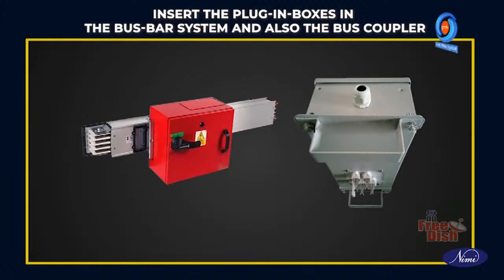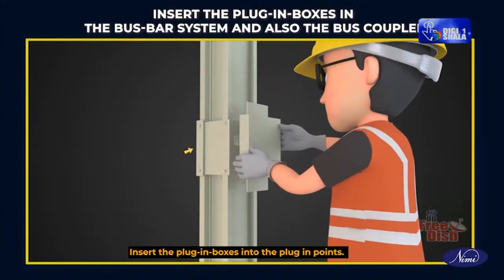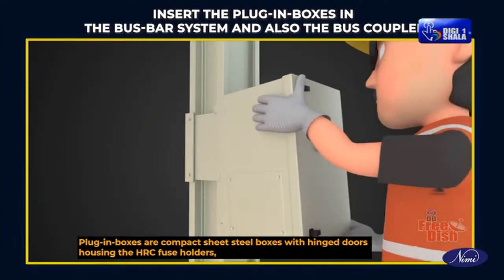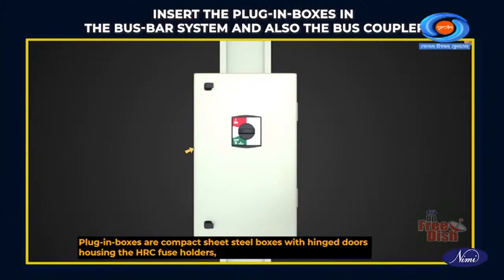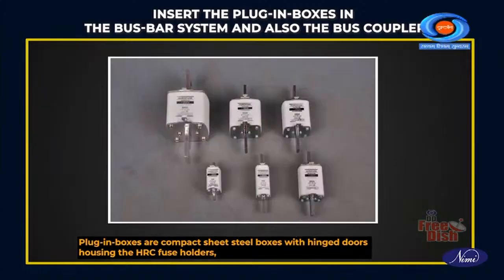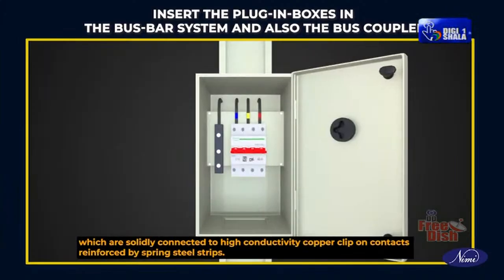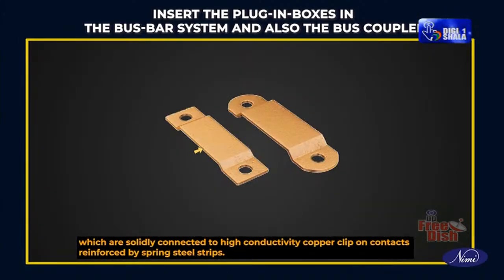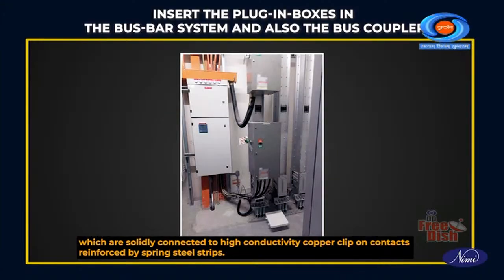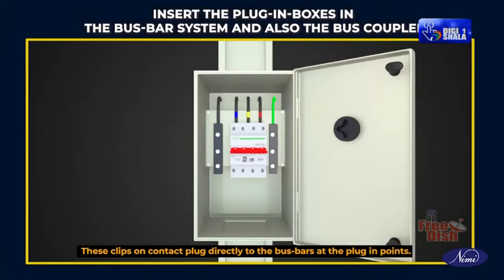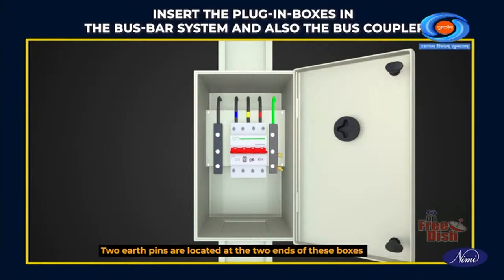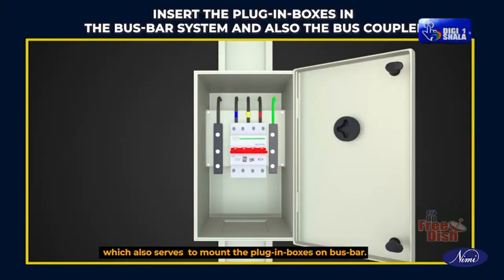Insert the plug-in boxes in the bus bar system and also the bus coupler. Insert the plug-in boxes into the plug-in points. Plug-in boxes are compact sheet steel boxes with hinged doors housing the HRC fuse holders, which are solidly connected to high conductivity copper clip-on contacts reinforced by spring steel strips. These clip-on contacts plug directly to the bus bars at the plug-in points.